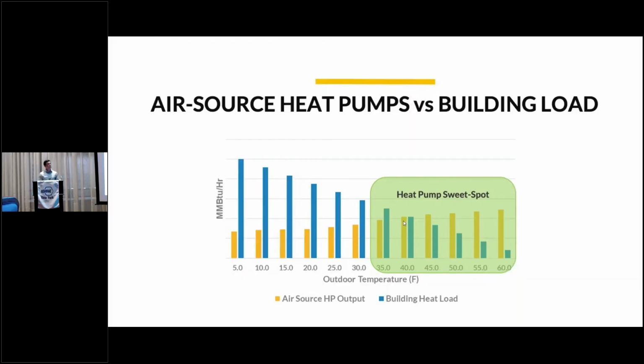So I plotted the building heating load in blue and the air source heat pump output in yellow. And as you can see, right around 40 degrees, we are fully covering the building's load. But one thing to note is that as the temperature gets colder, two things are going to happen. One, you have fewer hours in the day that are actually at those temperatures. A majority of your temperatures are going to be in that mid-range temperature bin. And two, your air source heat pump is actually going to derate itself. The capacity is going to decrease because it's harder to pull heat out of the cold air. And so this is charted by capacity, MMBTU per hour.